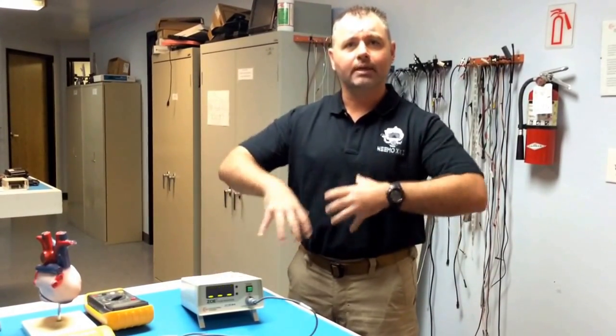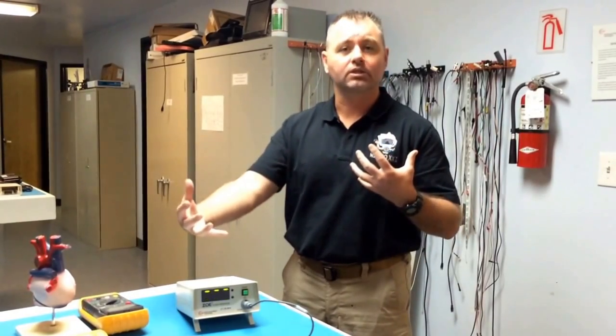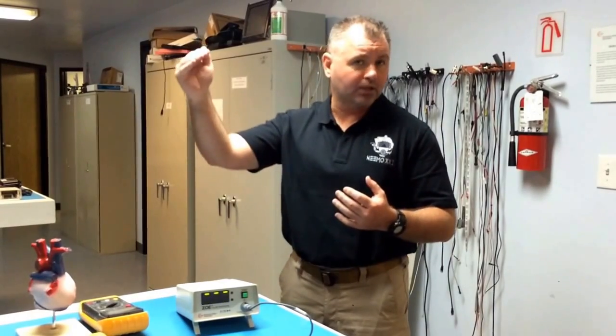The ZOE Fluid Monitor is a bioimpedance monitor. It uses a technique called bioimpedance to measure the fluid status or hydration status of patients — or in this case astronauts — as part of the NEEMO mission. The technology works by applying a small current to the body. We have a known voltage in that we measure the resistance or impedance to detect changes in fluid status. Effectively, the higher the number the drier the patient, the lower the number the wetter the patient.